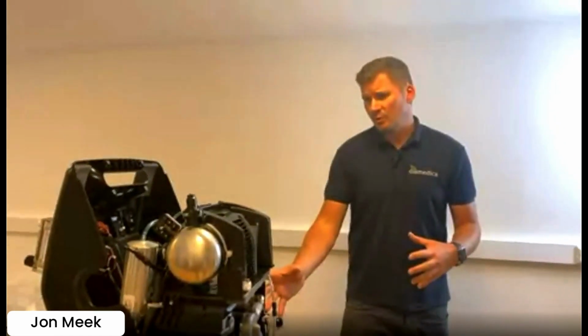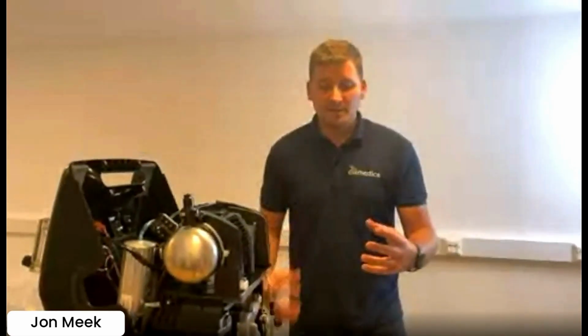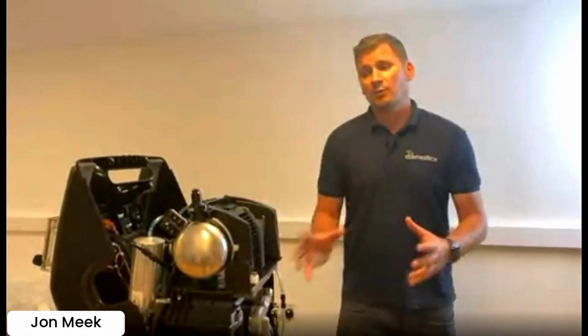The other question was, do the modifications affect power consumption? So, no, it doesn't. The compressor runs at a certain speed. Because it's an AC compressor, it runs at one sole speed only. So what happens is, even if we're taking off air from the machine, it's still drawing the same amount, 670 watts, as it would if we weren't using the machine. So it doesn't increase the power consumption for the CPAP compared to what it was with the concentrator.